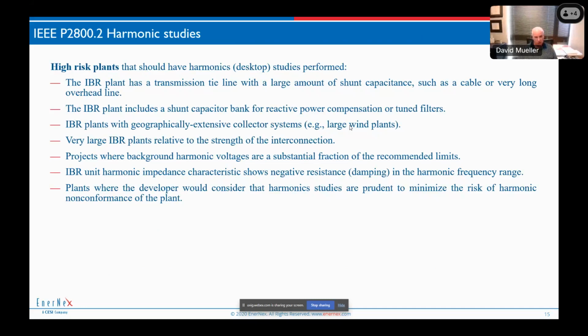So in other words, for some plants, perhaps studies don't need to be performed in advance. Maybe for some plants that don't have much of a risk factor, we're okay with building them and doing a post-generation measurement campaign, let's say, just to show that everything's okay. If you want to know what the high risk plants are, let's look at these bullets real quick. If it has a significant T line or certainly an underground cable, any offshore wind plant is high risk.